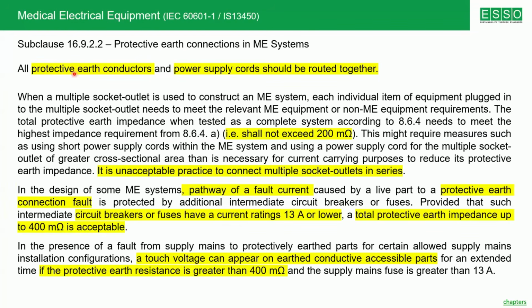The standard further, subclause 16.9.2, you can further see all protective earth conductors and power supply cords should be routed together. In earthing or in electrical installation, it is always a mandatory requirement that all the live conductors as well as the protective conductor shall be routed together. It should run together. Here also you can find the same clause. It is unacceptable practice to connect multiple socket outlets in series.